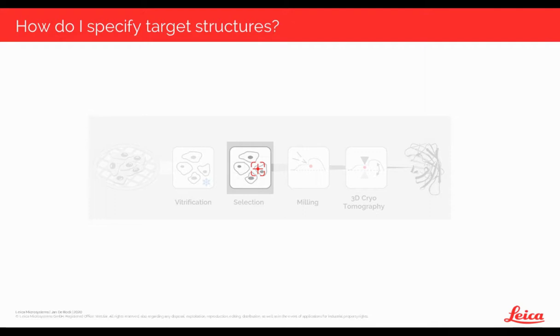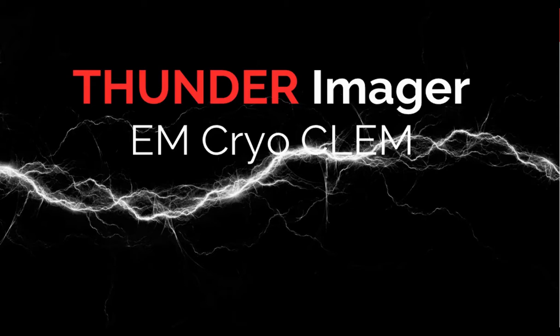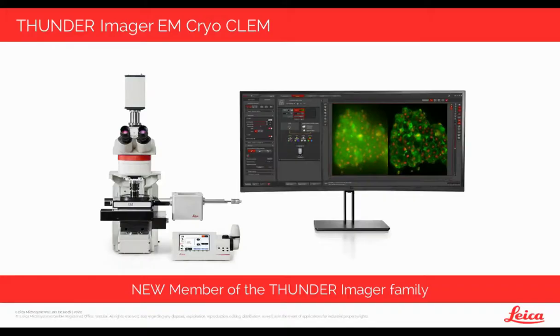The fluorescence microscope must be a cryogenic system, keeping the sample vitrified at all times during transfer and imaging. I am proud to introduce the Thunder Imager EM CryoCLEM, which serves exactly these needs. The Thunder Imager CryoCLEM is a fully motorized, upright, camera-based microscope, and it belongs to a whole family of imaging systems providing the new Leica Thunder technology.